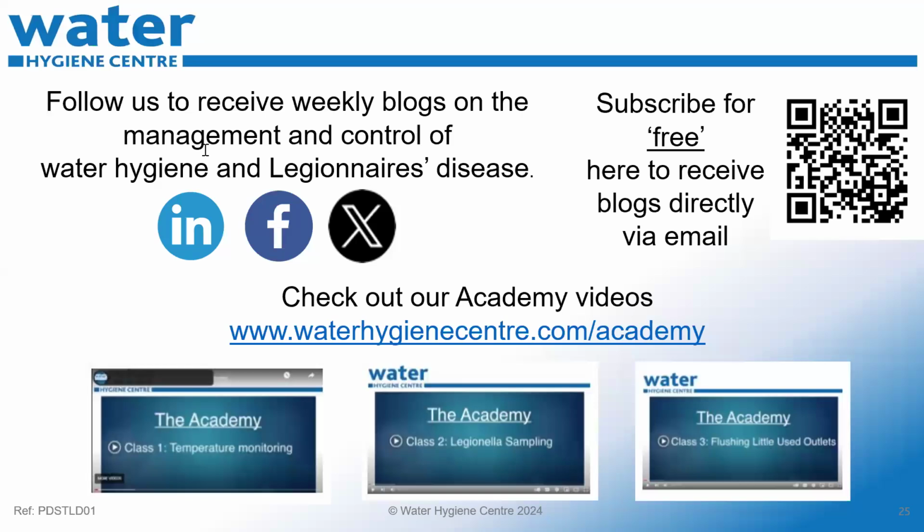Alexis says, reference premises with TMVs. Can people be reminded of where to test? Because I frequently find they are checking after the valve and not before it. I wish they would all be reminded of where to test. Yeah, that's again a competency assessment of the person doing the testing, because they're unaware of what the system layout is and what equipment is on site. So that's a lack of training and competency of the person doing the test of the outlets.